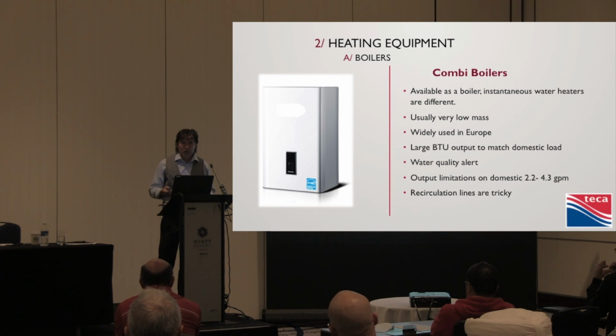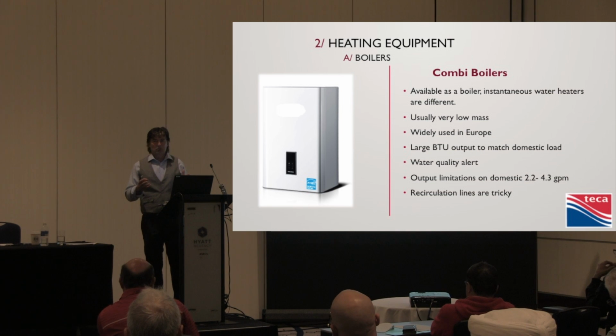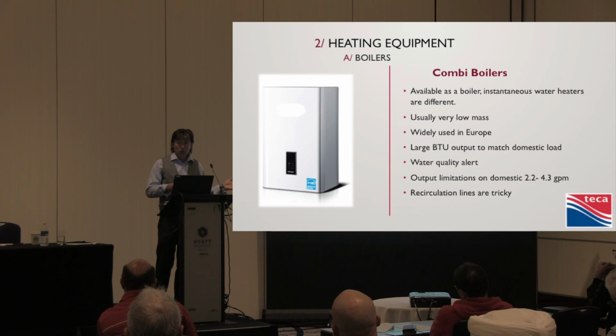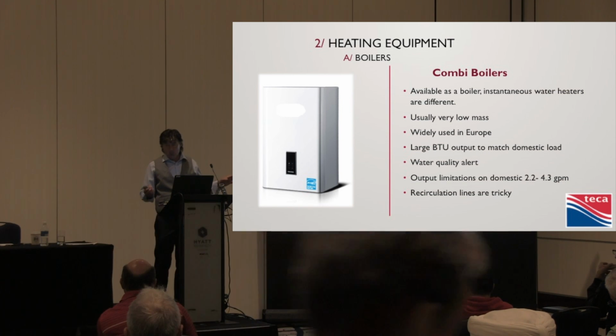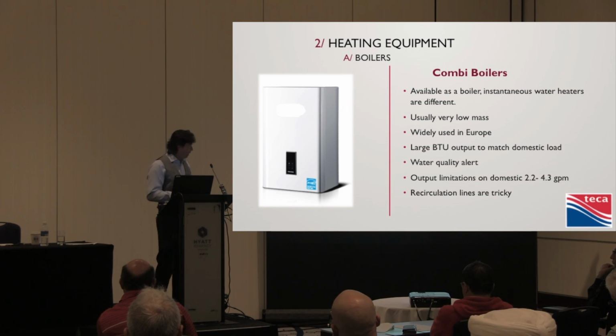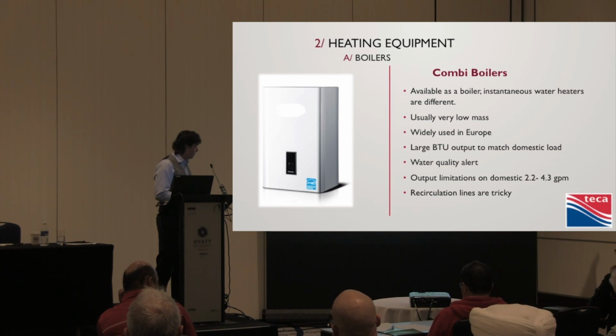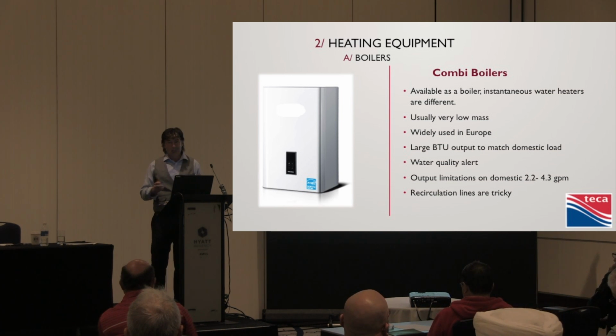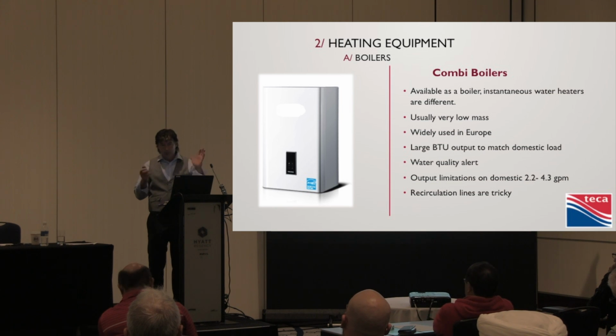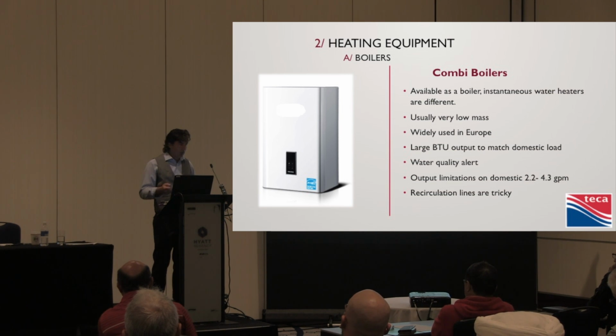Well, let's think about it. Shower head by code has got to be what? 2.5. But that's all the water coming out of the head. So when we size these things, usually 1.5 on the hot, 1.5 on the cold. So let's say it's 1.5. One shower head, 1.5. So we've used up 1.5 of our 2.2 with one shower head, in theory. Now, it all depends on a few different things, and what temperature and how much of the actual volume you're using. But if we got to size it by something, let's say 1.5.